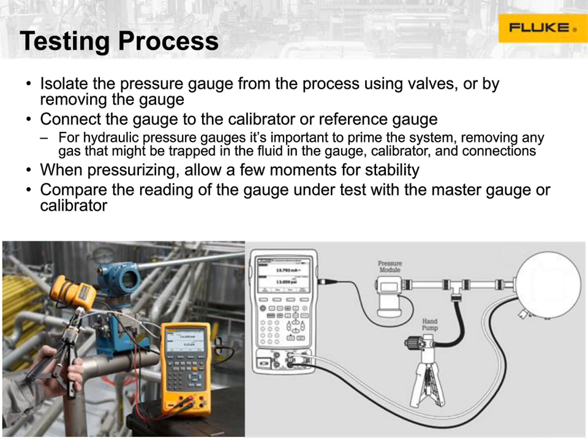So looking at the testing process, it's pretty straightforward. You basically isolate it. You connect the gauge to whatever you're going to use as a calibration reference. So I've got pictures here of a Fluke 754, but I've seen very, very accurate gauges be used to calibrate gauges. As long as you have enough test uncertainty ratio, that's okay.